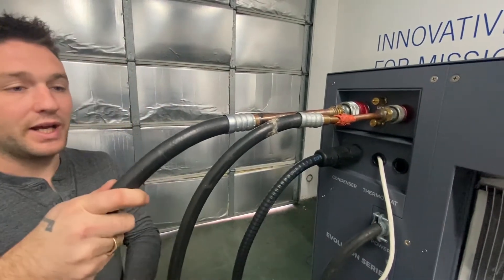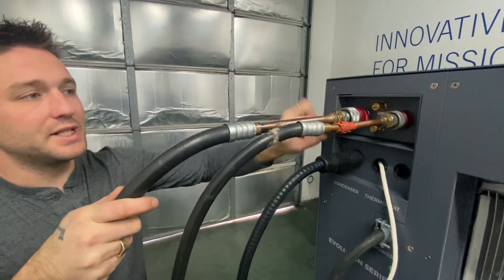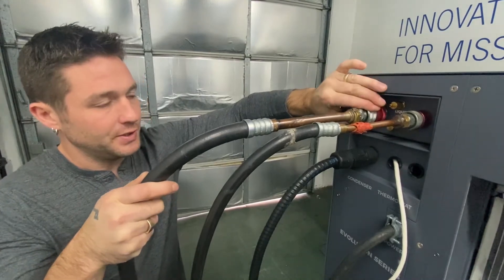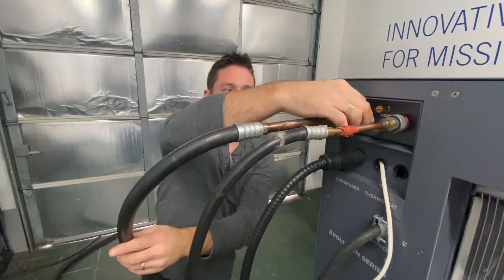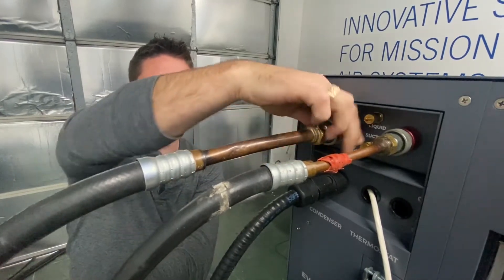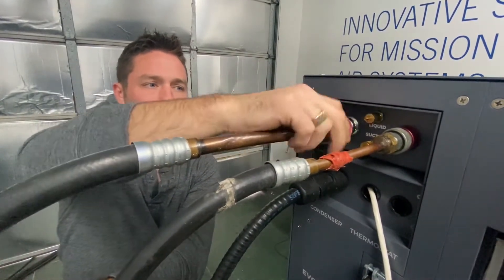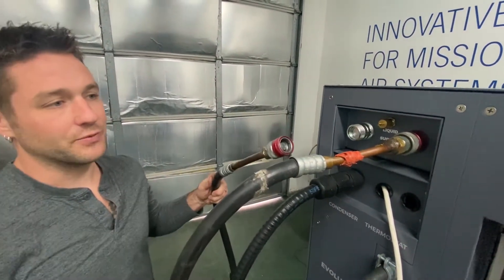The plug and play plumbing fittings, or refrigeration fittings, utilize a snap lock fitting. To remove this fitting, you simply pull back the red collar and twist the silver nut. This allows quick installation or removal of line set systems without the loss of refrigerant.